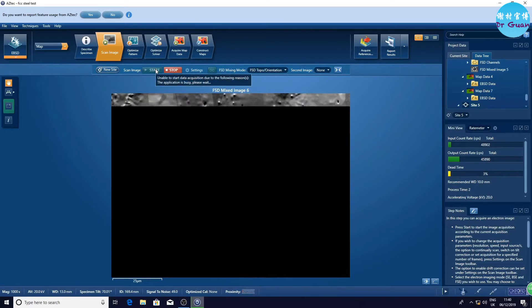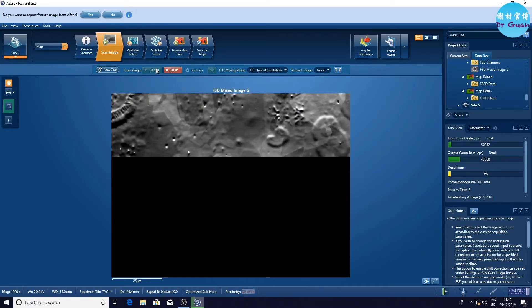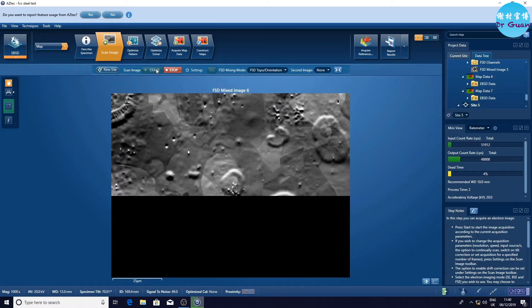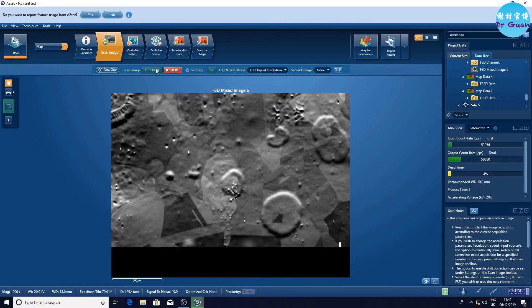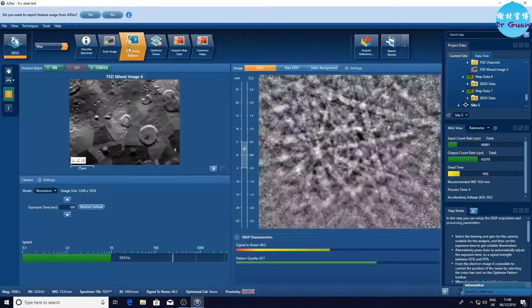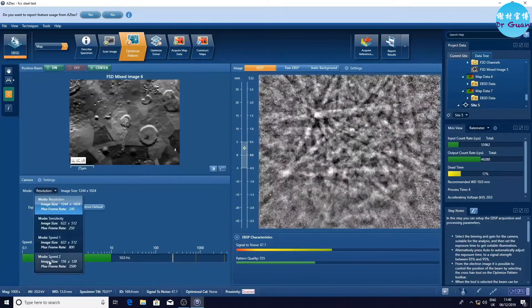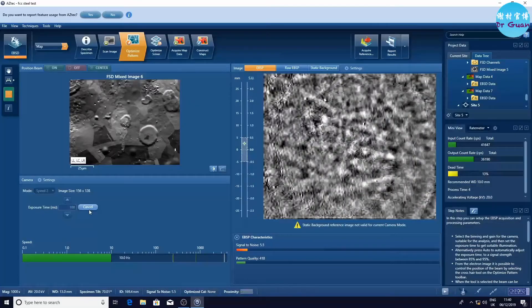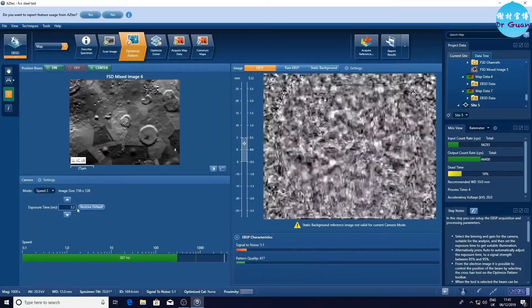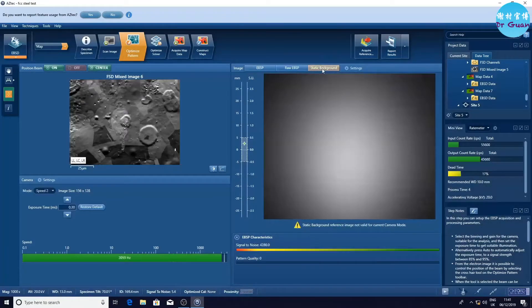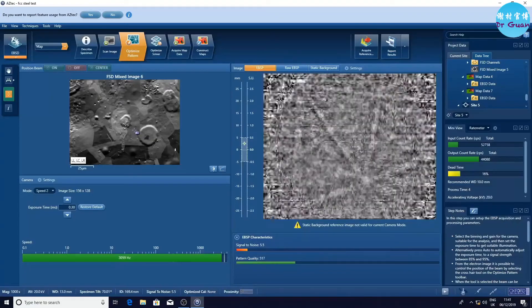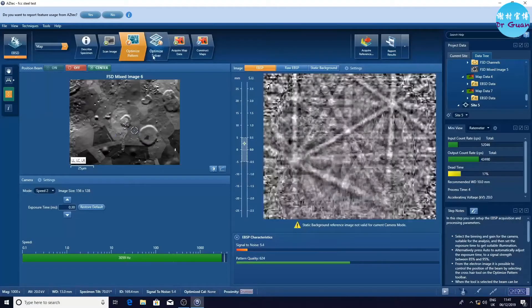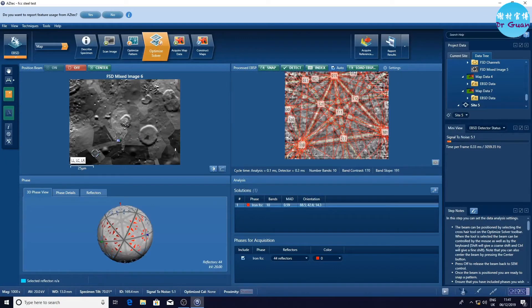Now we are going to do the EBSD and EDS at the same time. First of all, we need to scan the same region we have done before. Now we need to optimize the pattern, so this time we choose speed 2 and exposure time 0.3. Check the Kikuchi pattern, which is not too bad. We can check the optimize solver.